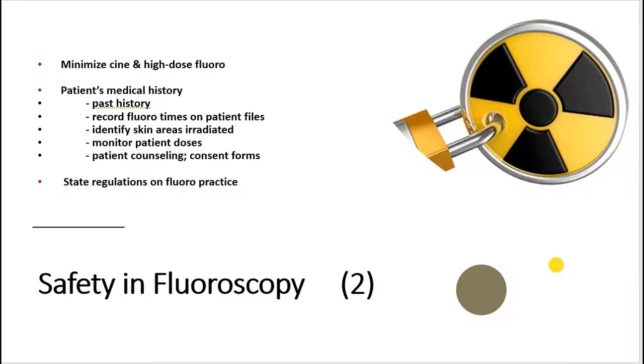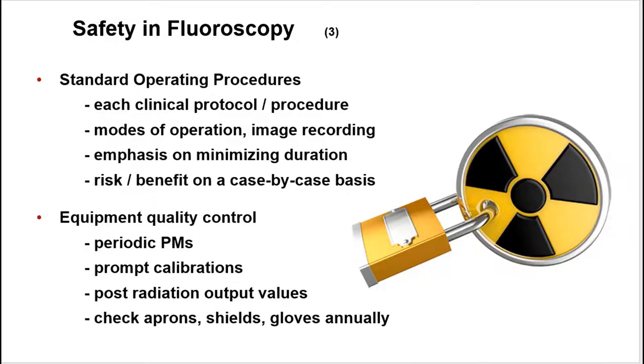You should be familiar with state regulations on the practice of fluoroscopy and with your patient's history. You need to record fluoro times on the patient's files, identify skin areas that have been irradiated, monitor patient doses, and at times use patient counseling and consent forms. Equipment quality control is essential — you need periodic preventive maintenance, prompt calibrations, posted radiation output values, and annual checks of aprons, shields, and gloves. Your facility also needs to have standard operating procedures.